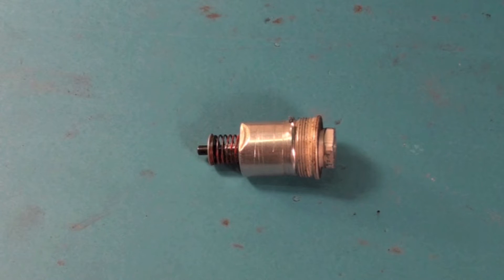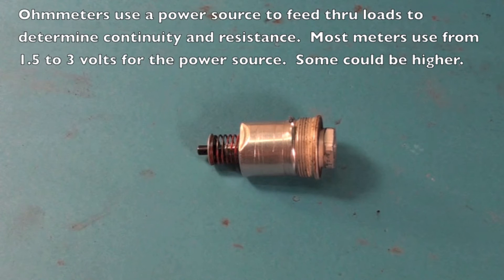I had a comment about pilot safeties like this one here, and if you wanted to check for continuity, you could check it with an ohmmeter. The comment was that if you used an ohmmeter that used nine volts, you could burn up the pilot solenoid winding. You could burn the winding out of it.